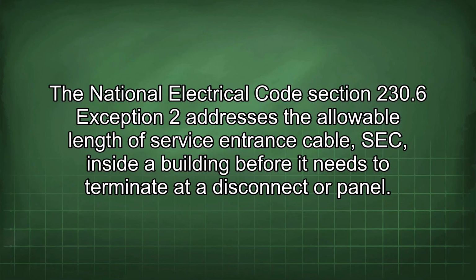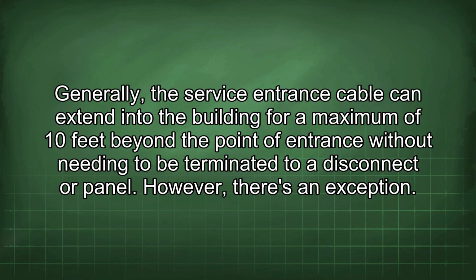The National Electrical Code Section 230.6 Exception 2 addresses the allowable length of service entrance cable (SEC) inside a building before it needs to terminate at a disconnect panel. Generally, the service entrance cable can extend into the building for a maximum of 10 feet beyond the point of entrance without needing to be terminated to a disconnect panel.